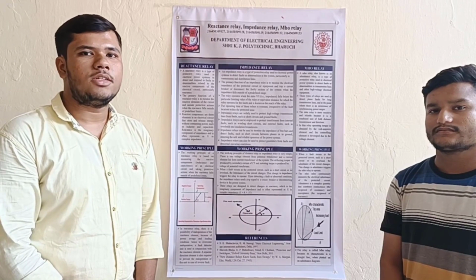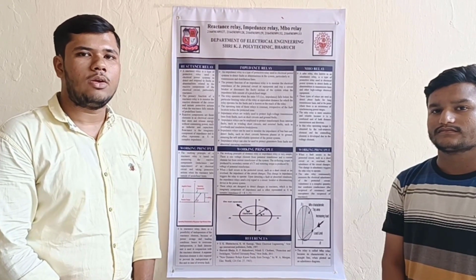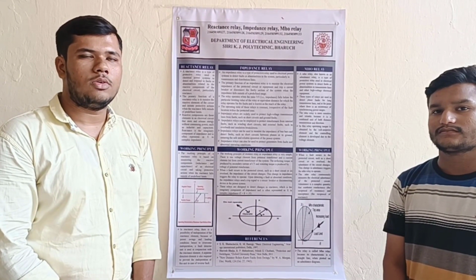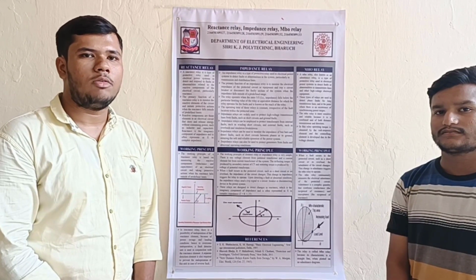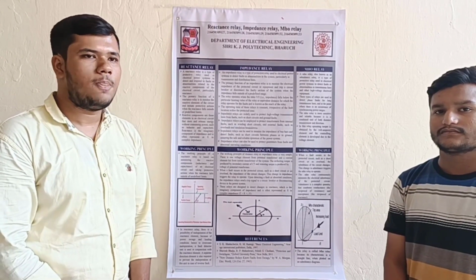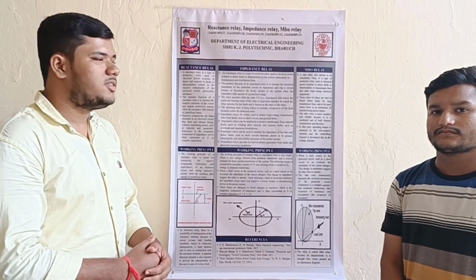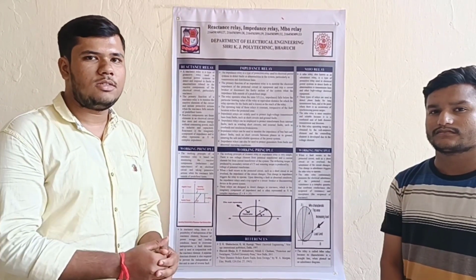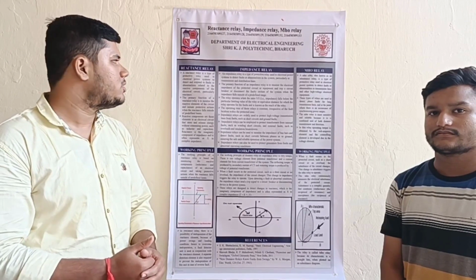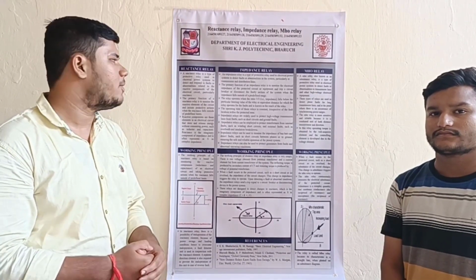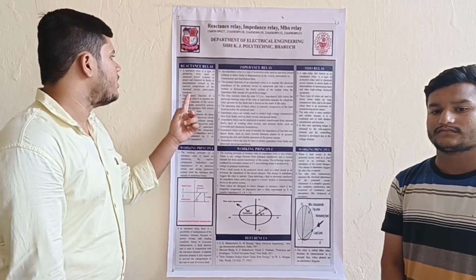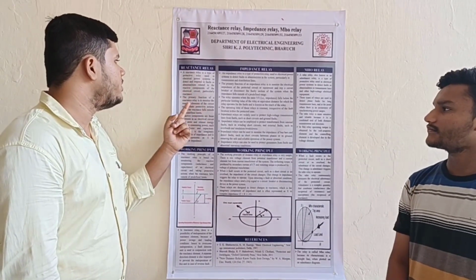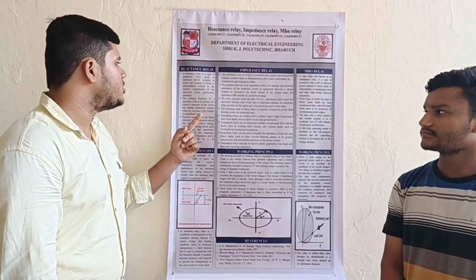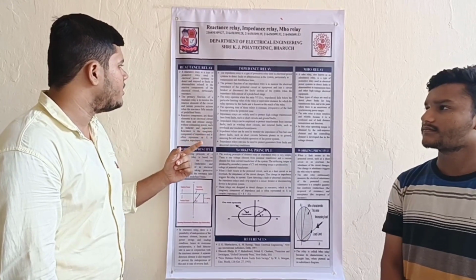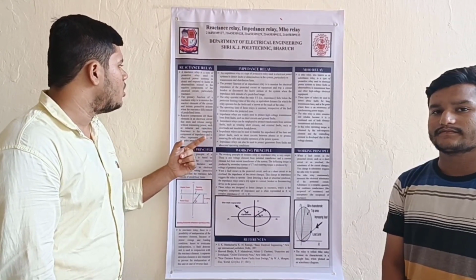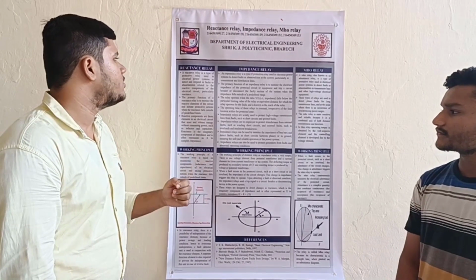Relay is an electrical switch that opens and closes the circuit when an outside source gives the signal. Then reactance relay is a combination of reactance plus relay. So now reactance relay is a type of protective relay used in electrical power system to detect and respond to faults or abnormalities related to the reactive components of the electrical circuit, particularly reactance.